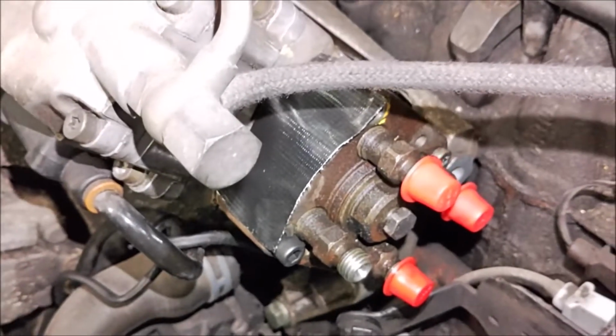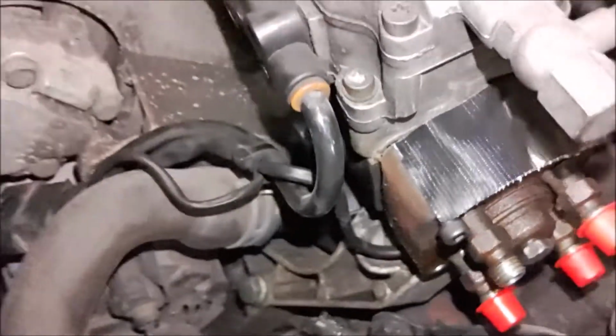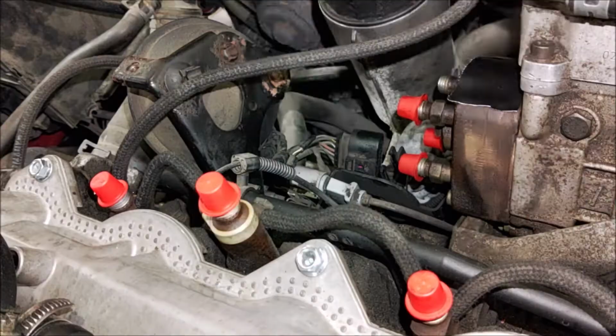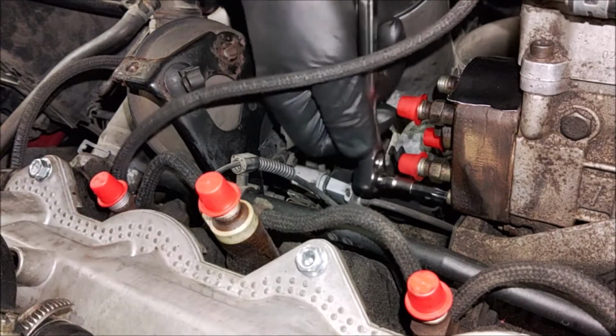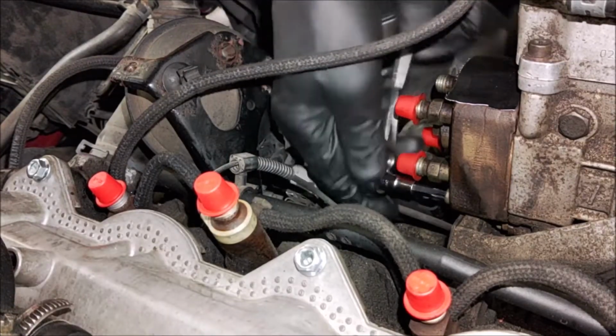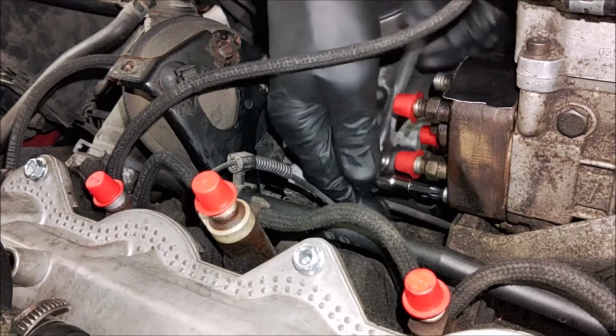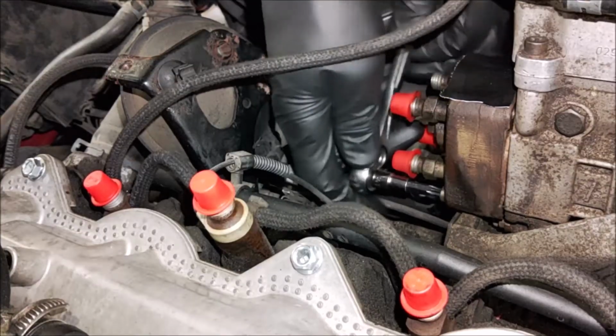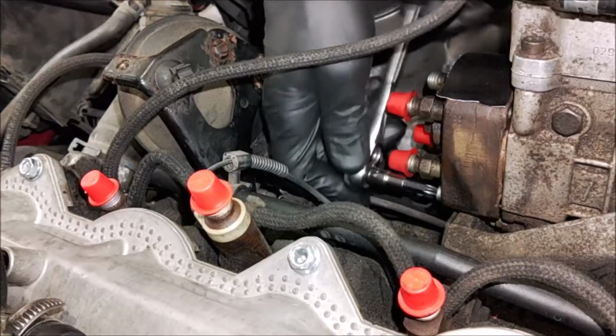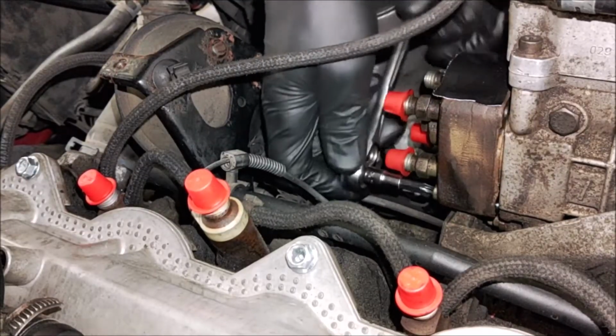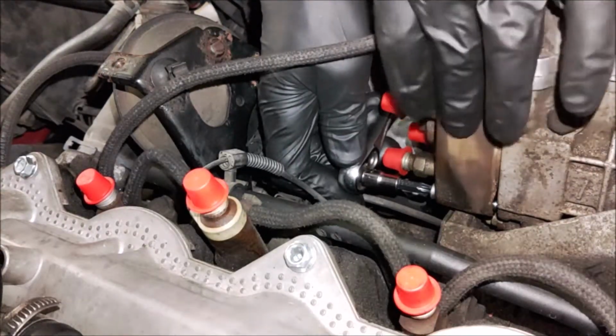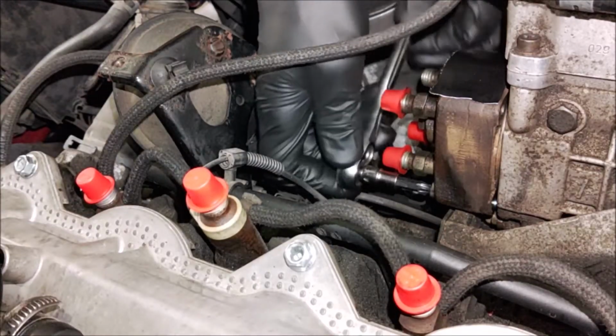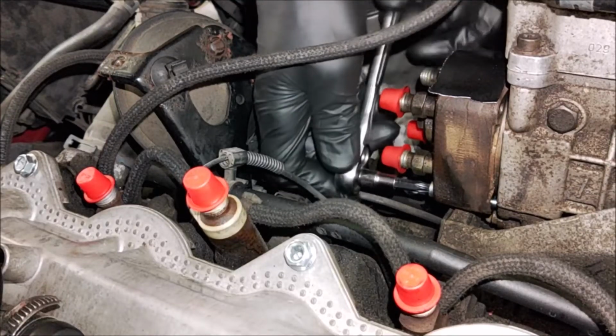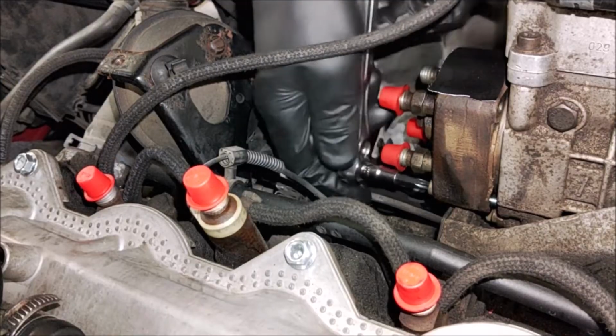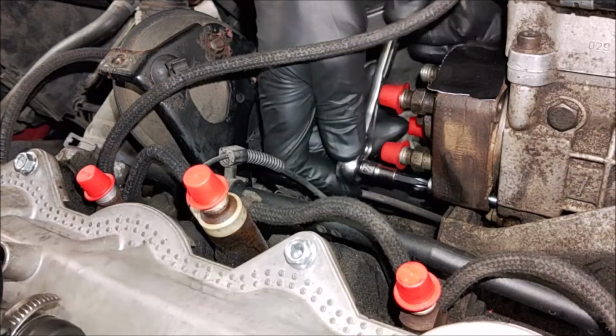So now we can slowly back out that bottom bolt, and the head should slowly separate from the pump body. It actually already is there, I see it. Okay, I'm going to slowly remove this opposing screw, and the head should slowly back out of the pump body. You can see the gap is increasing. The spring is pushing this head from the body, and slowly our seal should become exposed. And you will have some fuel that leaks out.